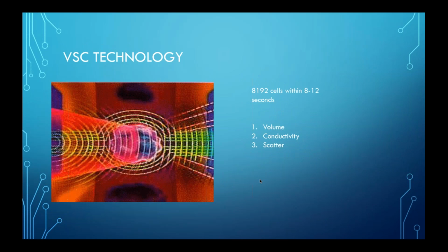What I just talked to you about was the Coulter principle. That was counting the cells from the CBC side. That's just the count. Now we get into the VCS technology. That's the differential count, which counts the white cells. What we used to count in 100 cells, this counts in 8,192 cells within 8 to 12 seconds. So it's a lot more accurate. It's counting a lot more cells than what we did. Out of all these cells that it's counting, it's identifying 5 specific different cells.